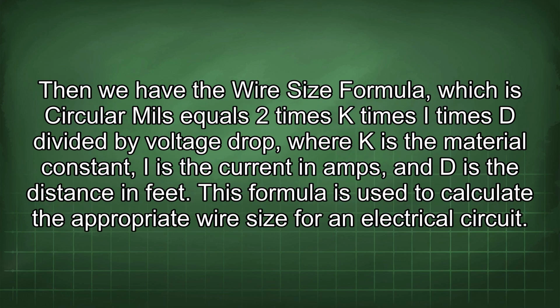Then we have the wire size formula, which is circular mils equals 2 times K times I times D divided by voltage drop, where K is the material constant, I is the current in amps, and D is the distance in feet. This formula is used to calculate the appropriate wire size for an electrical circuit.